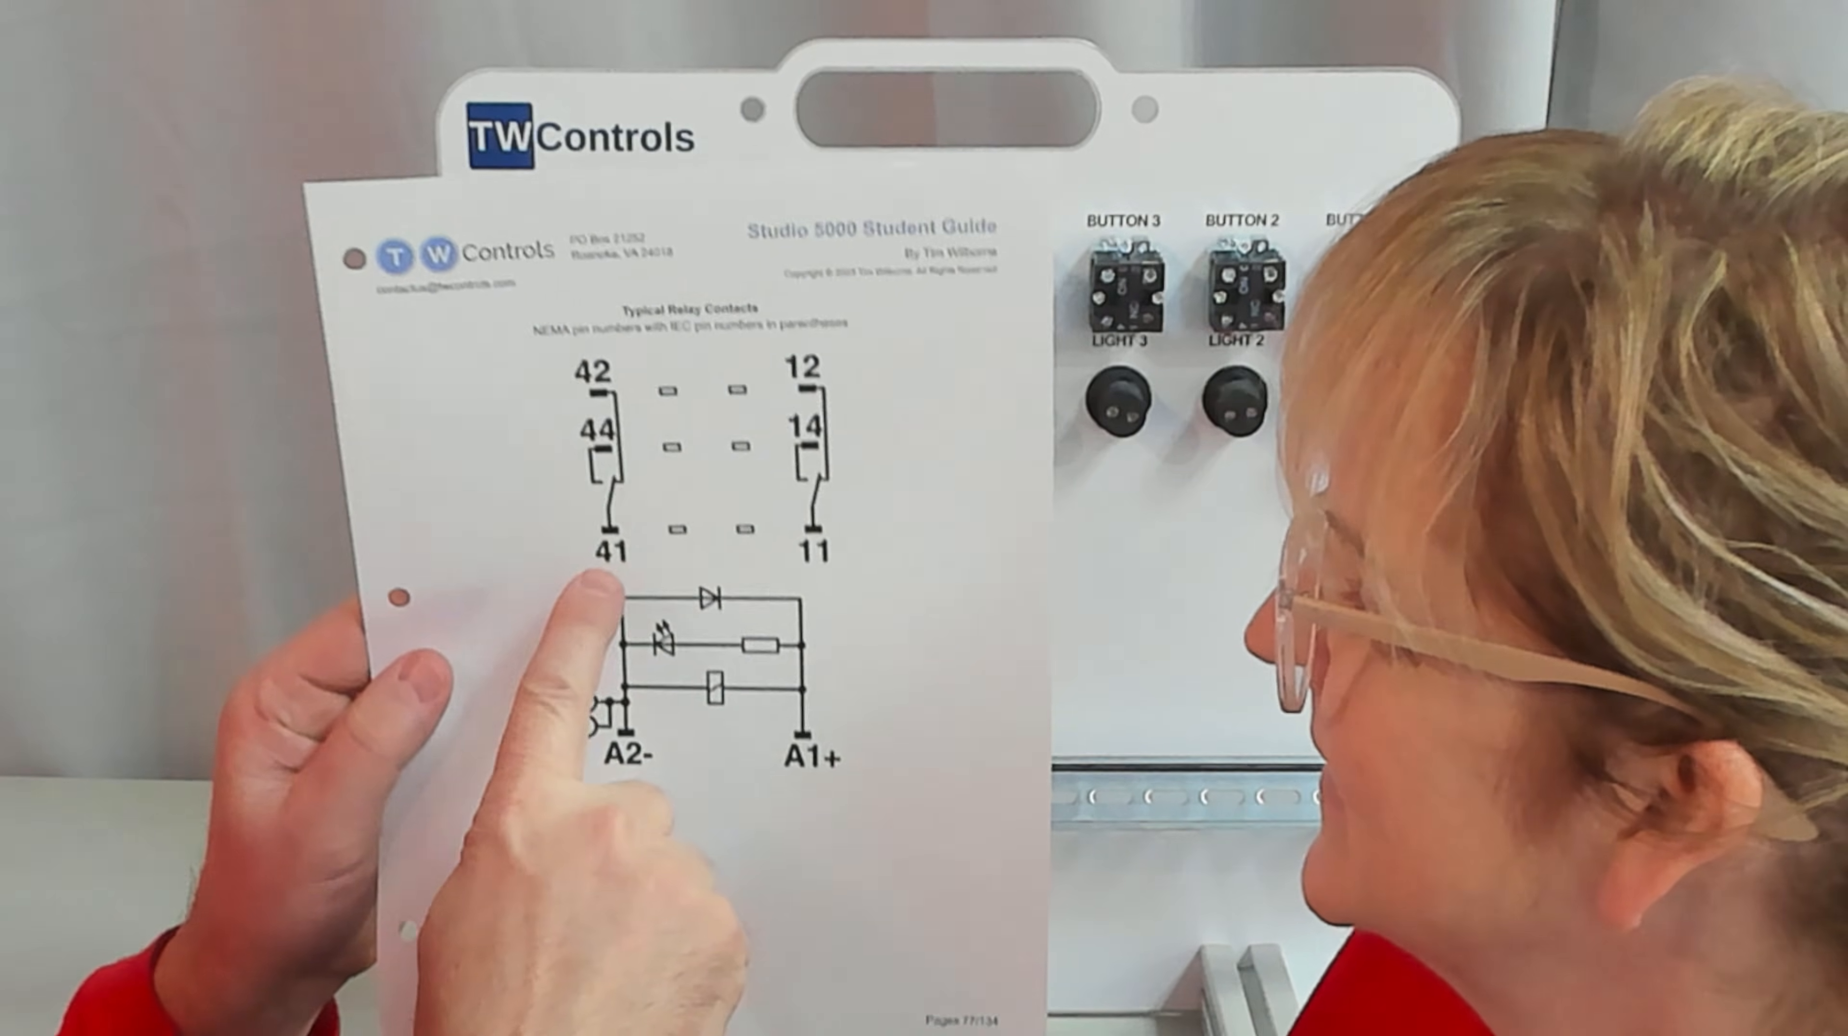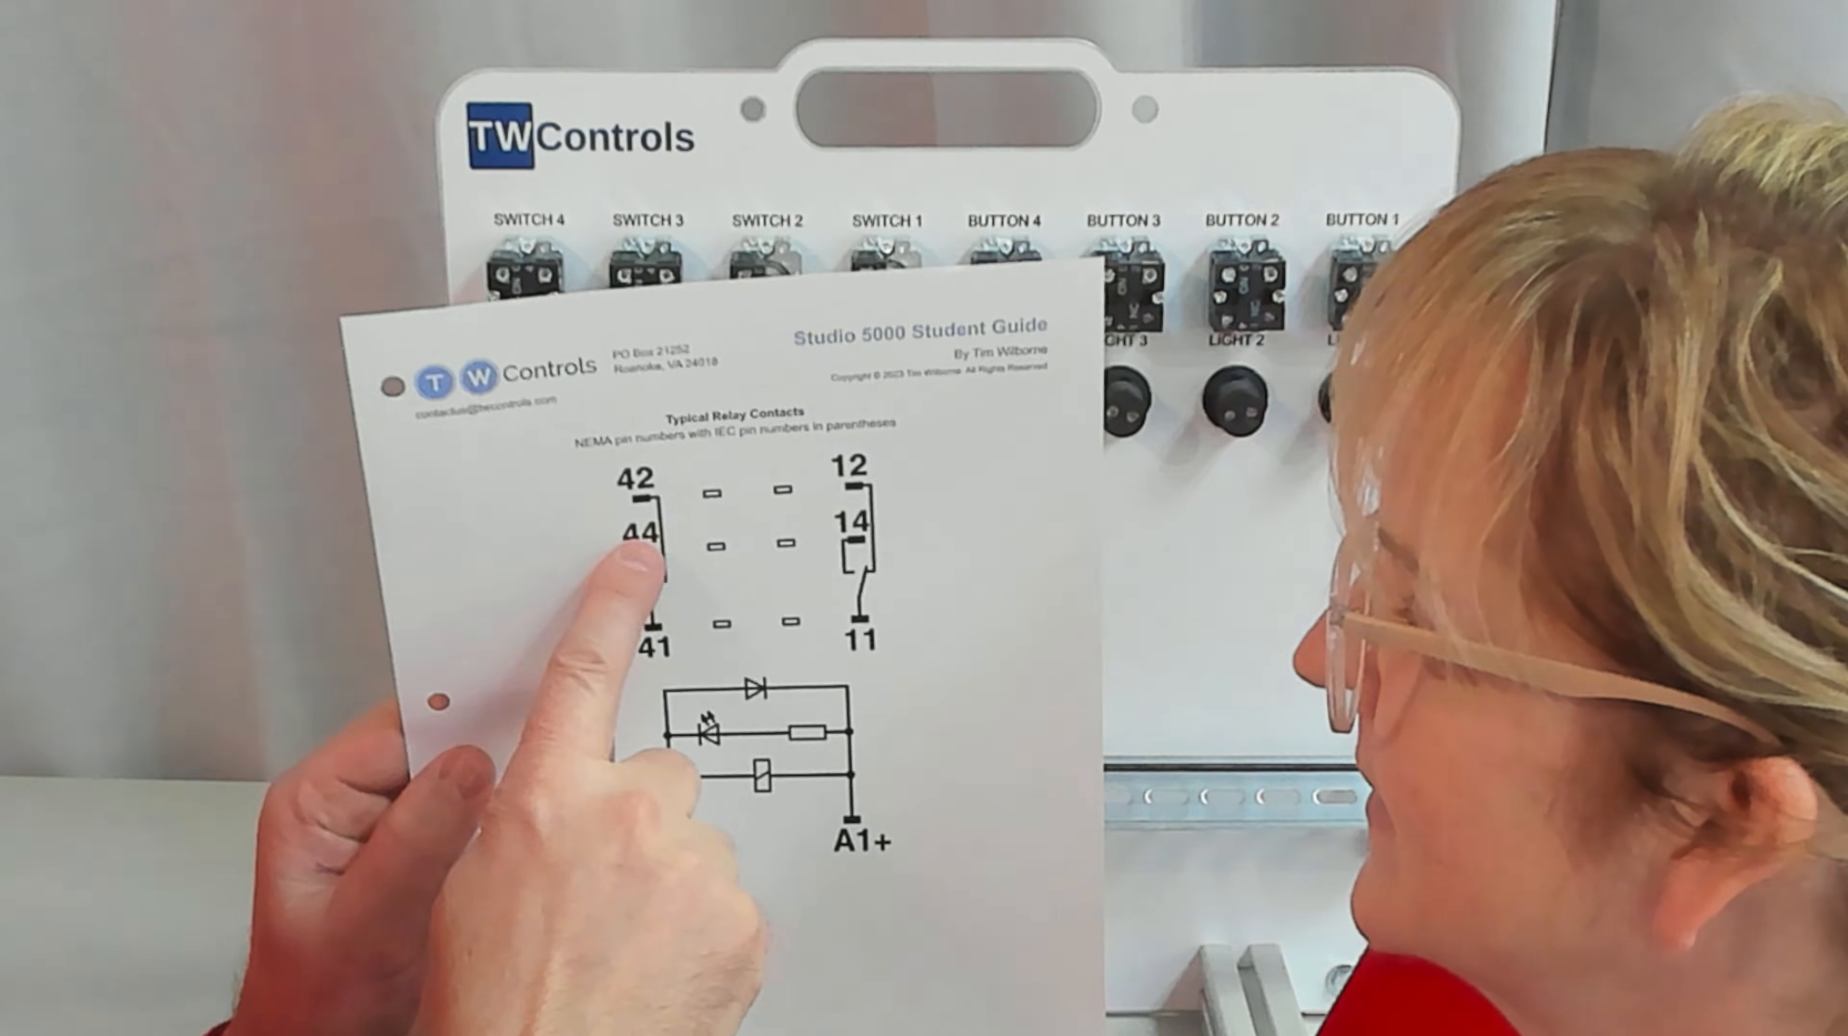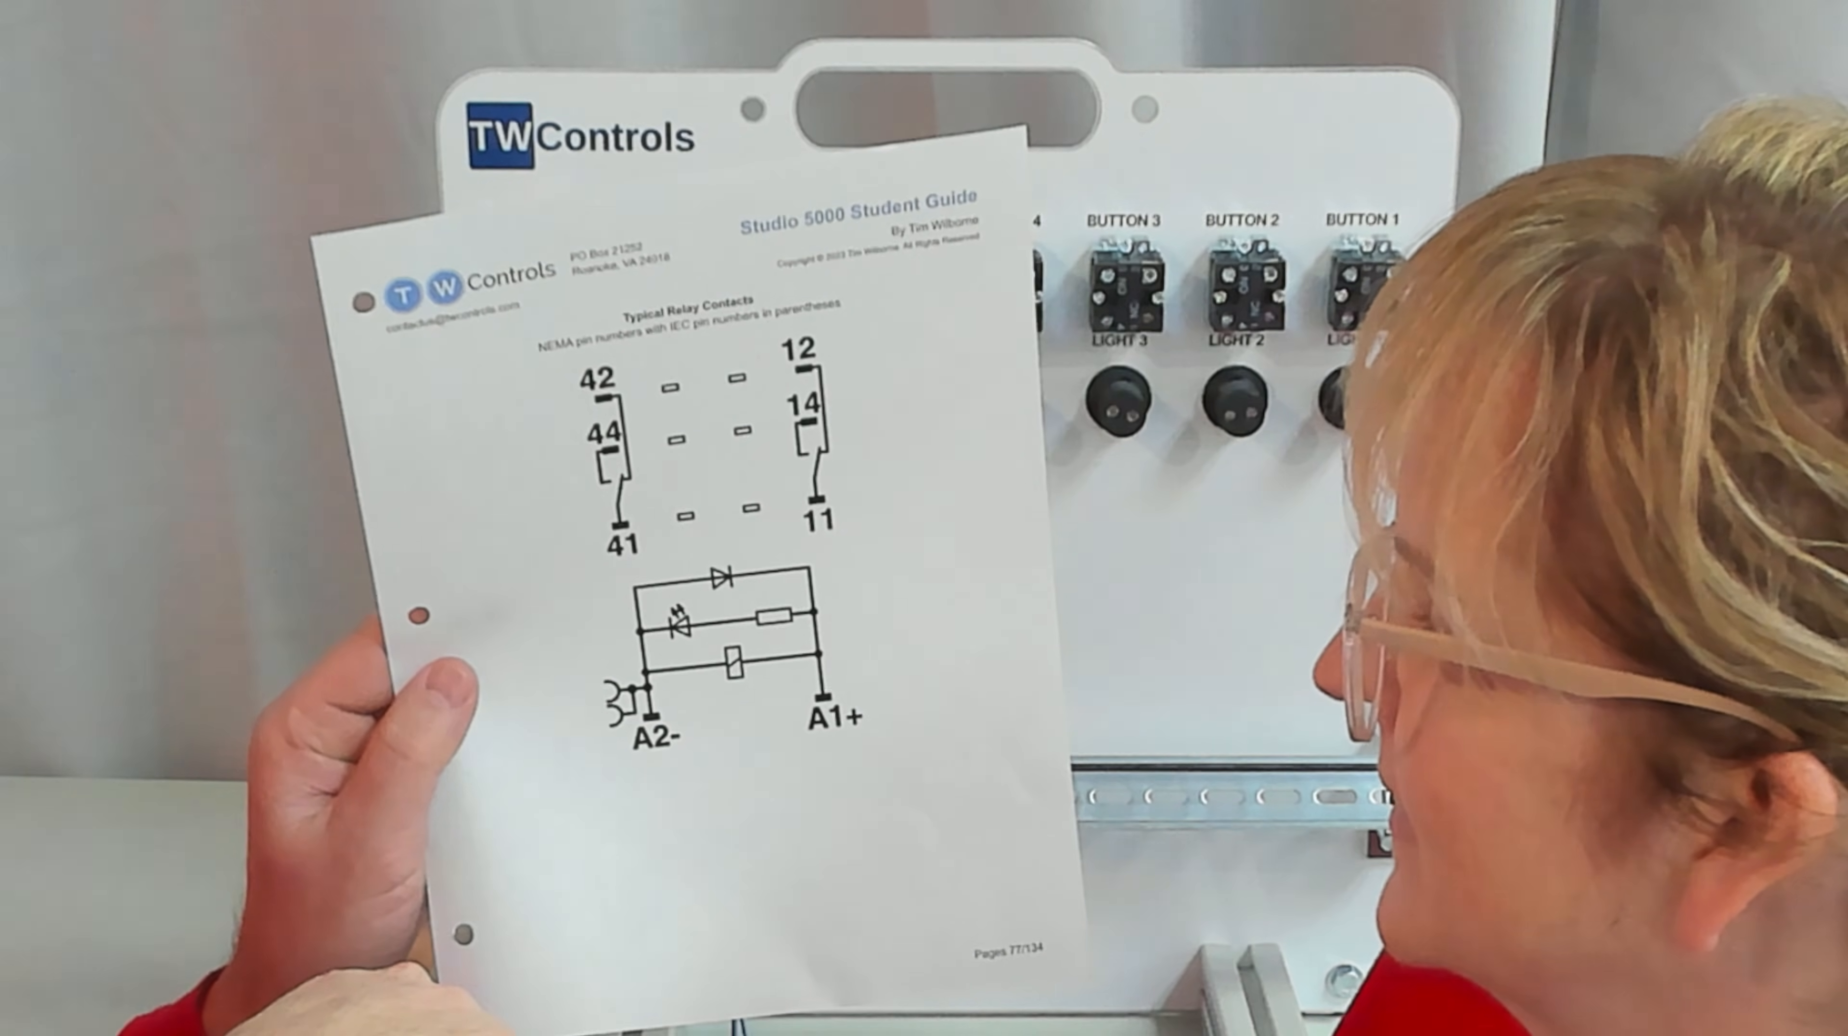Now we can take a wire from the plus 24 volt to 41 to feed power to that contact that we're switching. And we're going to take a wire from 44, which is the normally open, to our green light. And then we're going to take our green light back to the minus of our power supply.